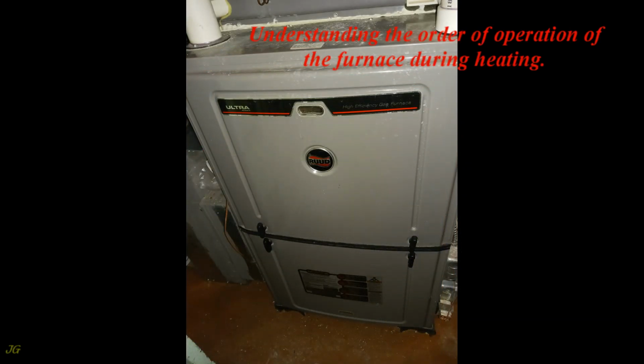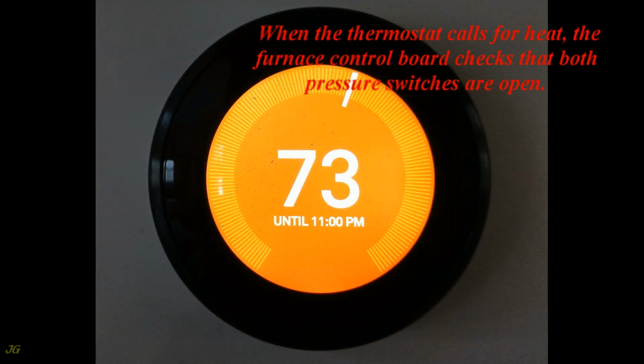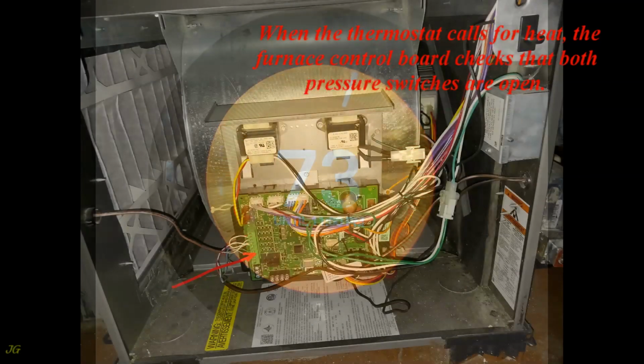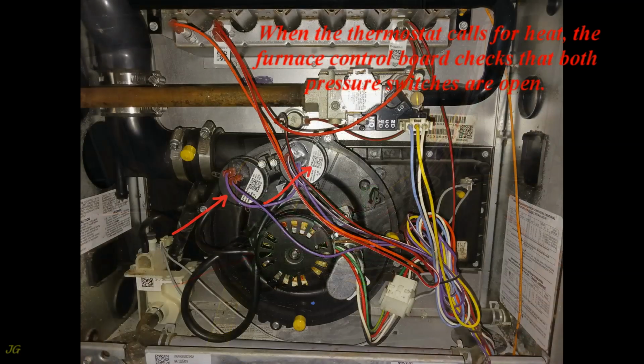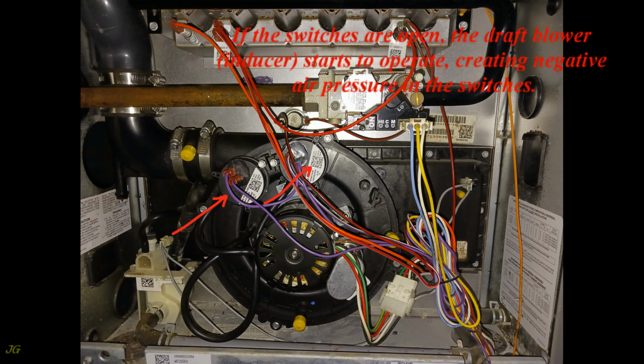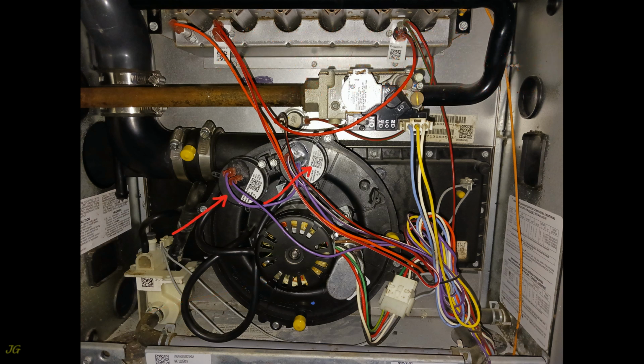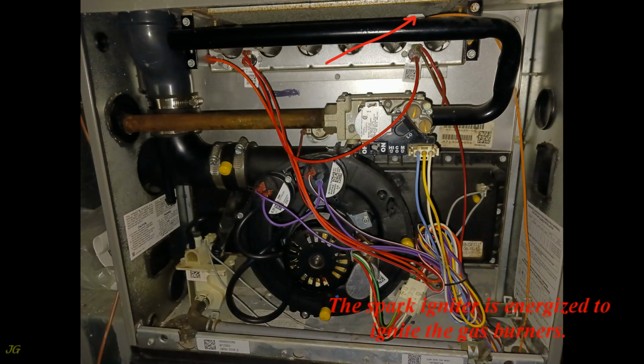Understanding the order of operation of the furnace during heating. When the thermostat calls for heat, the furnace control board checks that both pressure switches are open. If the switches are open, the draft blower, inducer, starts to operate, creating negative air pressure in the switches. Negative air pressure closes the switches and the gas valve opens for ignition. The spark igniter is energized to ignite the gas burners.